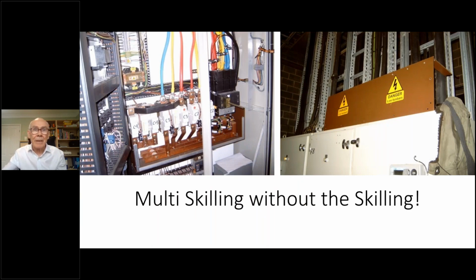This is an example where I had to stop a young man working inside this panel in a refrigeration room. He was undertaking diagnostic testing with a multimeter above bare 800 amp bus bars, which you can see at the bottom there — they shouldn't be bare, but that's another question. On further questioning, it turned out this lad had very little experience, and the height of his qualifications was an NVQ level 2 in refrigeration, which would take perhaps weeks to achieve in the UK.